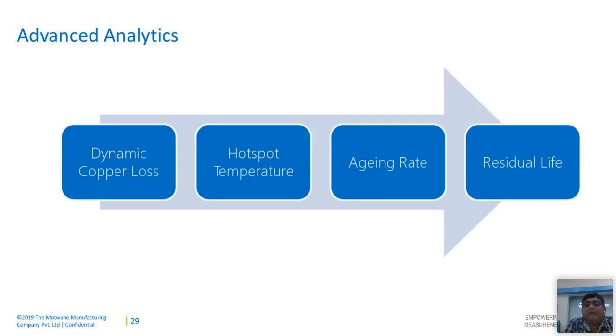And as all would be aware, once this depolymerization sets in because of the hotspot exceeding the limits, it is an irreversible kind of damage. So it's very essential to capture this in real time. Now, residual life is based on the design life and the rate at which the transformer aging is happening, based on the thermal model, and that is what is represented.